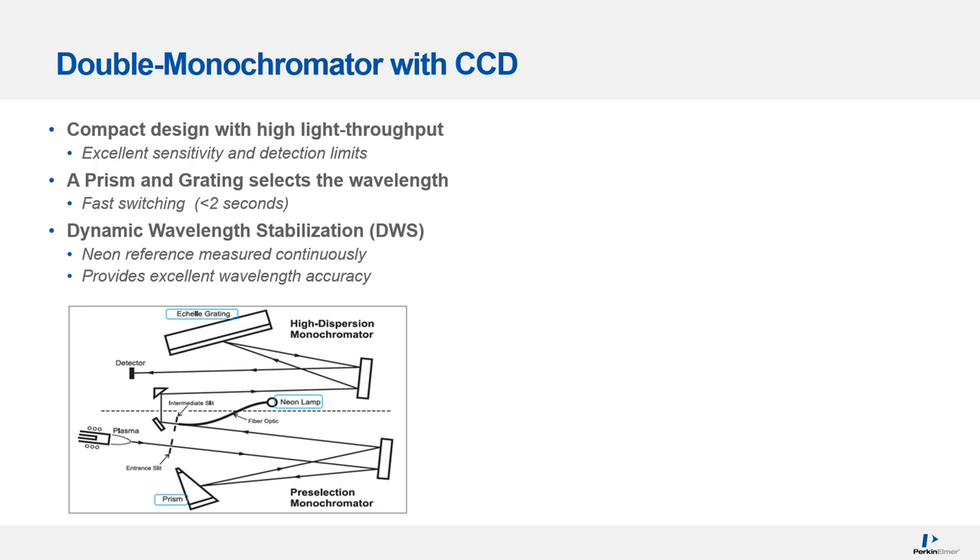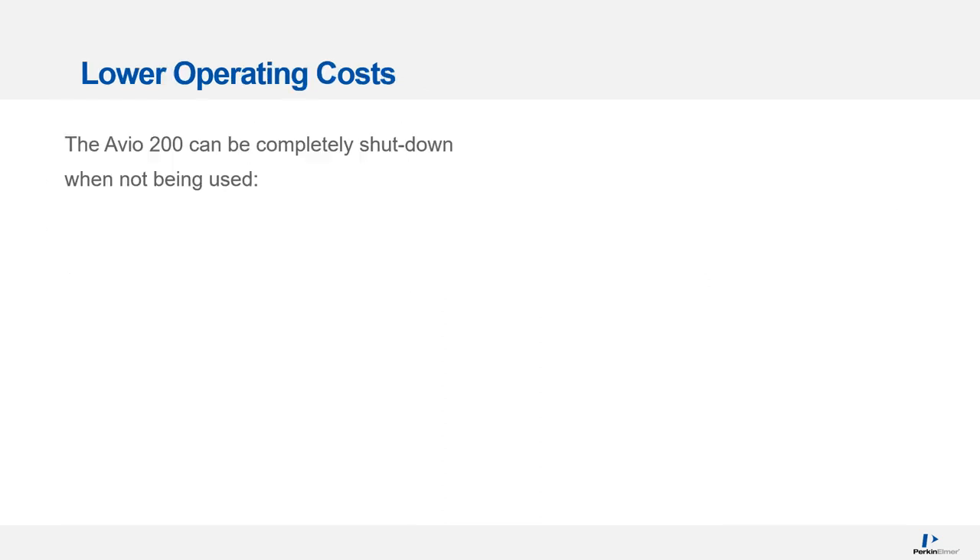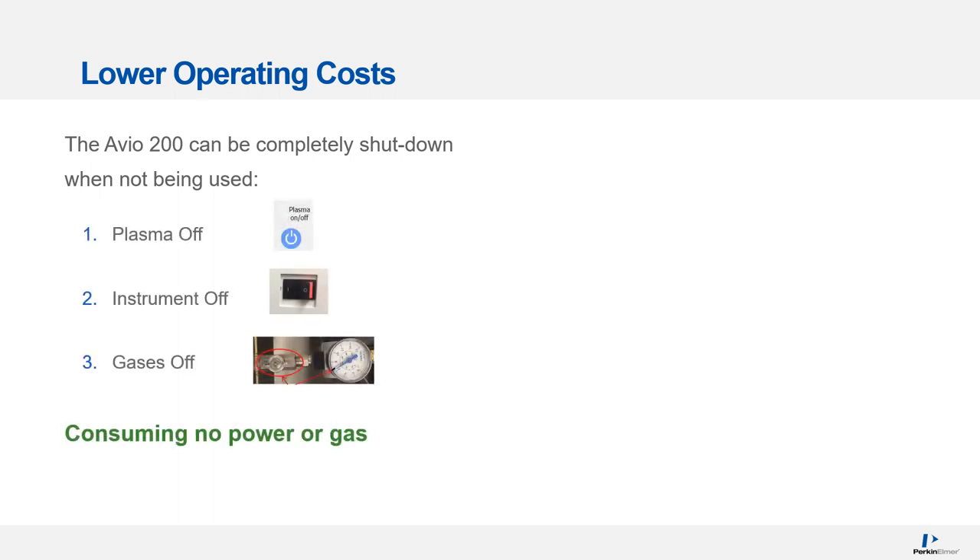Dynamic wavelength stabilization is also the reason why the spectrometer on the Avio 200 doesn't require thermal stabilization. The CCD detector is separated into two regions: the bottom part measures the analyte emission and the top part measures the neon reference beam. The CCD detector also provides simultaneous background measurement, which is important for good accuracy and precision. One of the other key benefits is that the Avio 200 can be completely shut down when not in use — the plasma switched off, the instrument powered down, and the gases turned off — consuming no power or gas, similar to how you would operate an atomic absorption spectrometer.